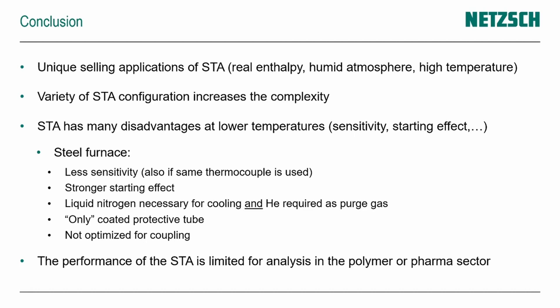Coming to the end of today's lecture, let me summarize. We looked at the STA — the combined TGA-DSC analyzer — and its unique points: real enthalpy determination, humidity measurement possibilities with accessories, and high temperature applications up to 2400°C. The STA is characterized by its modularity — the ability to exchange furnaces, sensors, and use various accessories — giving us the ability to design an instrument customized to application needs. There is a complexity aspect, but we will help you find the correct instrument.